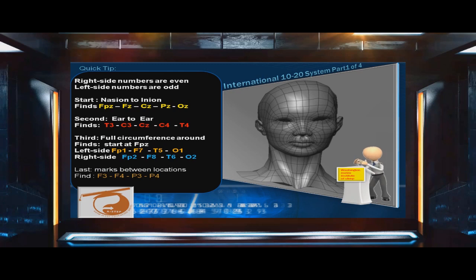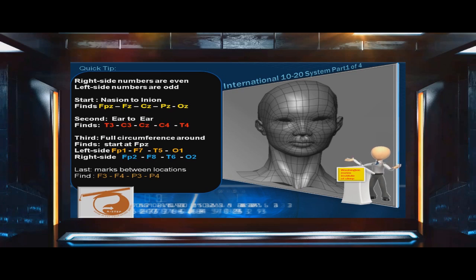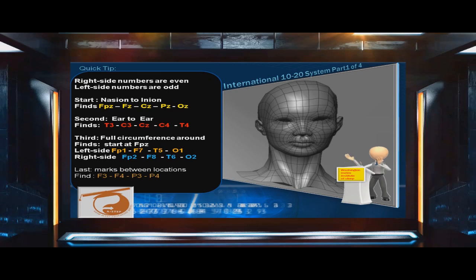Second, measure from ear to ear. This will help you find locations T3, C3, CZ, C4, and T4. Third, measure a full circumference around your patient's head, starting at the FPZ location in the center of the forehead. On the left side, this will help you find landmarks FP1, F7, T5, and O1. On the right side, you'll find locations FP2, F8, T6, and O2.